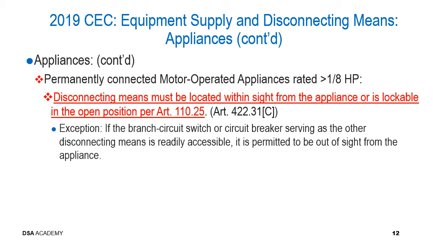As we all know, most circuit breakers that provide overcurrent protection for downstream equipment or components are generally inside of a panel, and the panel has a door on it. So even though those circuit breakers are accessible, they are not considered readily accessible. So that's an important distinction to make here when you've got motor operated appliances that are rated over 1/8 horsepower.